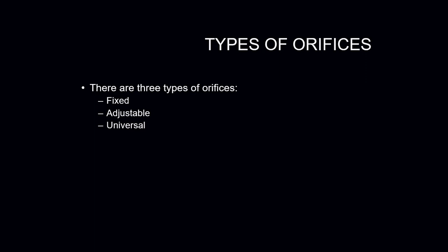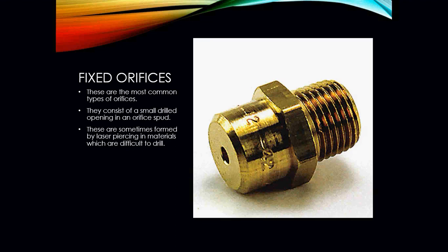There are three types of orifices we will run into in the HVAC industry: the fixed orifice, the adjustable orifice, and what is called the universal orifice. The fixed orifice is the most common type you're going to run into in residential settings. They consist of a small drilled opening in the orifice spud, and they're sometimes formed by laser piercing into the material, which is difficult to drill.